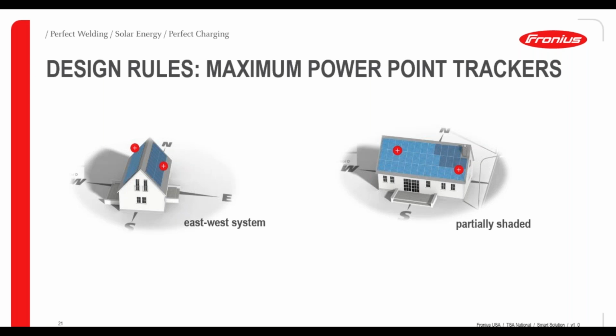And this is shading with a system using a string inverter, correct? That is correct. As I said, just having the ability of isolating those strings on different MPP channels makes it possible to build a system where you cannot avoid the shade. So we want to break that myth that string inverters can't be used in the shade. Obviously, our first option is to always mitigate shade or design around the shade, but in instances where there may be some partial shading, we can always isolate those shaded modules to a different channel and have the maximum production out of our unshaded modules on a separate channel. Yeah, I think that's a big misconception.